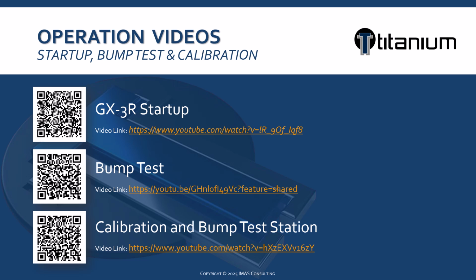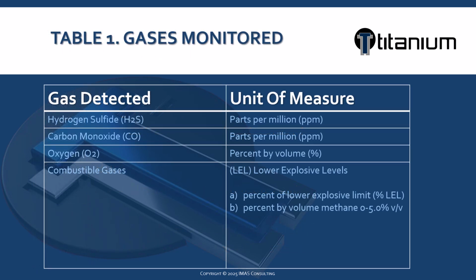Click the following QR codes or video links to learn the procedures for startup operations of the model GX-3R and how to bump test, calibrate the 4-head personal gas monitor. This table explains the units of measurement for the personal 4-head gas monitor sensors. Hydrogen sulfide, otherwise known as H2S, and carbon monoxide are measured in parts per million, while the oxygen and the LEL combustible gases are measured in percentage.